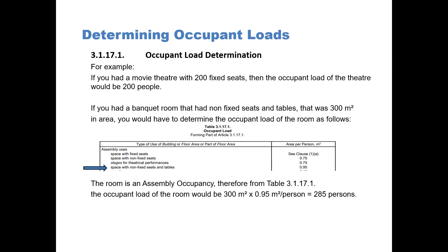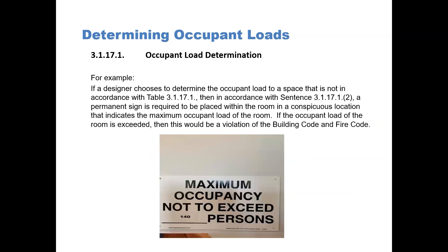This gives you a value of 285 persons, so this banquet hall would be able to hold, in accordance with Table 3.1.17.1, 285 persons. Another example is where a designer chooses to determine the occupant load to a space that is not in accordance with Table 3.1.17.1, as permitted in the article. As per sentence 3.1.17.1.(2), a permanent sign is required to be placed within the room in a conspicuous location indicating the maximum occupant load of the room. If the occupant load of the room is exceeded at any time, this would be a violation of the building code and the fire code.